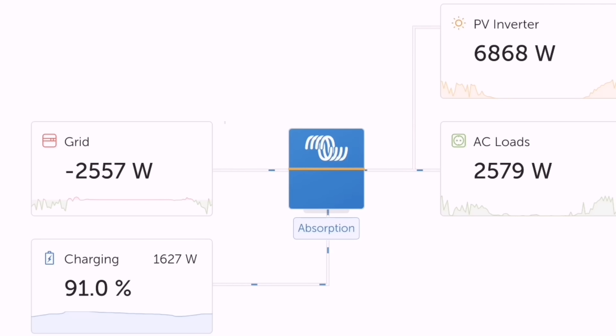There was some discussion about 3.6 kilowatts continuous not being what we should get. But remember — 3.6 kilowatts of charging is going into the battery at 50 volts. It's not based on 240 volts. So if it's a 70-amp charger with a 50-volt battery, that's 3.5 kilowatts; so 3.6 kilowatts peak is absolutely what I'm expecting. To deliver that 3.6 kilowatts of charging, it does take just over 4 kilowatts of AC power — that may be where the confusion lies, looking at the power from the grid versus what's actually going into the battery.